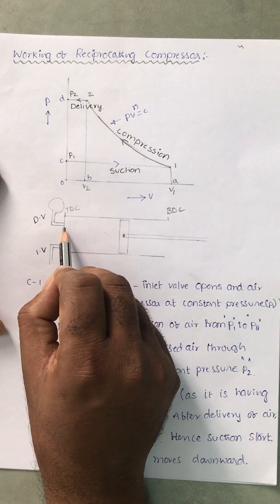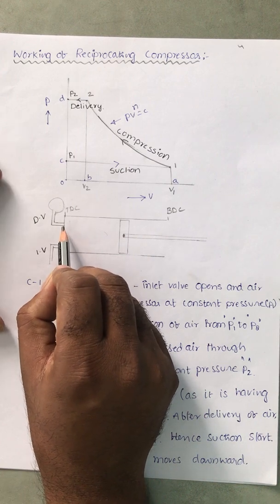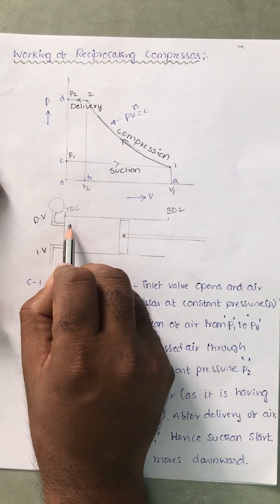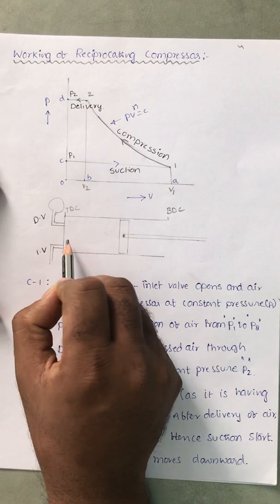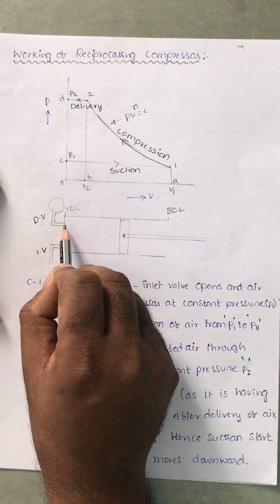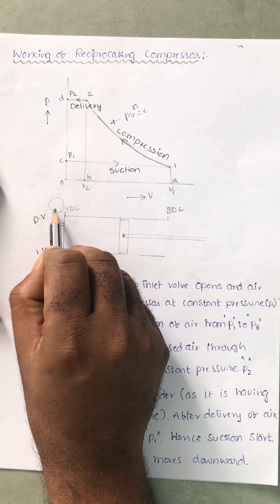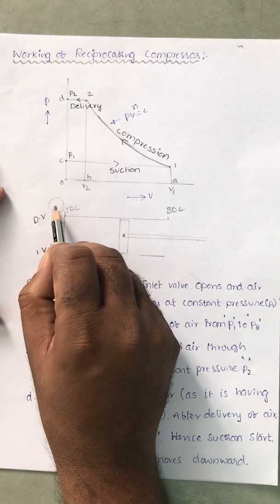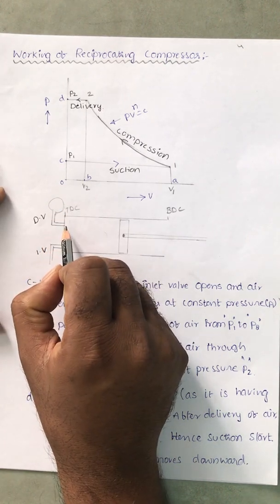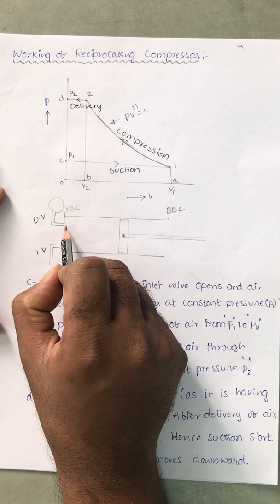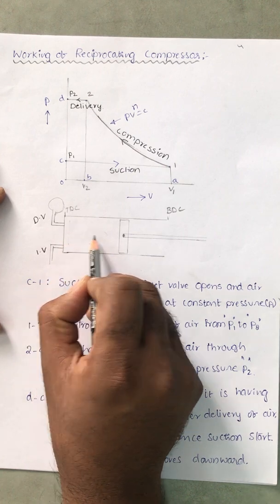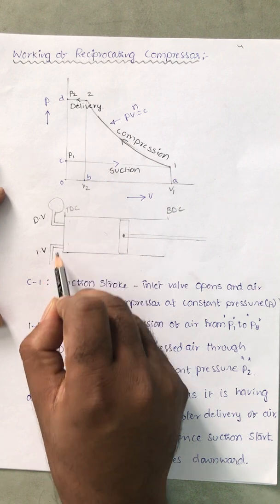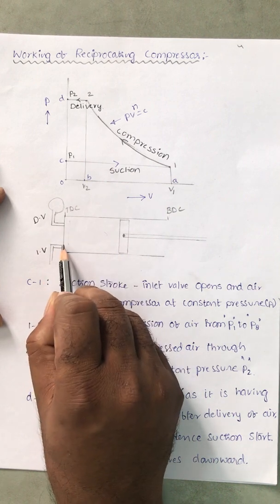Compression of air takes place until the piston almost reaches the top dead center. The delivery valve remains closed until then. Once the piston almost reaches the top dead center, the delivery valve opens and this compressed air under high pressure is sent to the container at constant pressure. Once the air is sent to the container, there is no air inside the cylinder, and the piston starts to move downward — that is the suction stroke. The delivery valve closes and the inlet valve opens again.